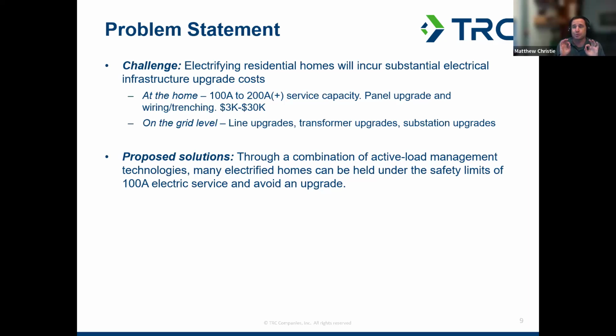$3,000 is extremely cheap and rare, that means you have an overhead line, the transformer is close by, the service drop can just be swapped out, the utility can schedule it quickly, and the panel replacement is about $1,000 for the panel and $2,000 for labor. It's easy because the wiring was simple and the old panel was well organized, so it can be swapped out fast, reusing the breakers and everything.